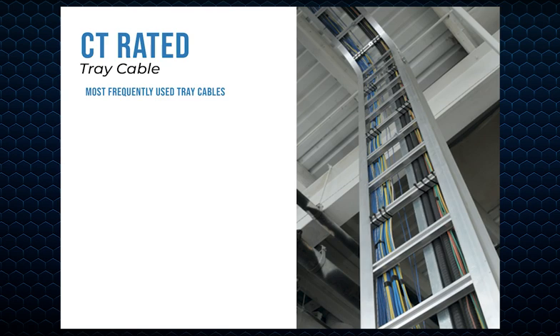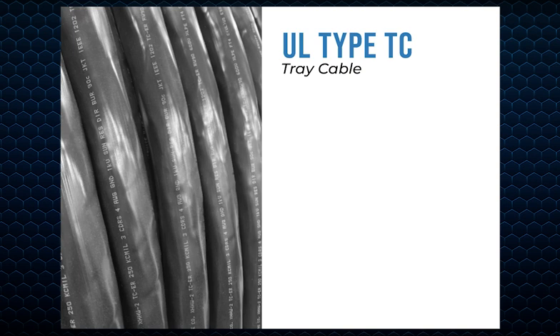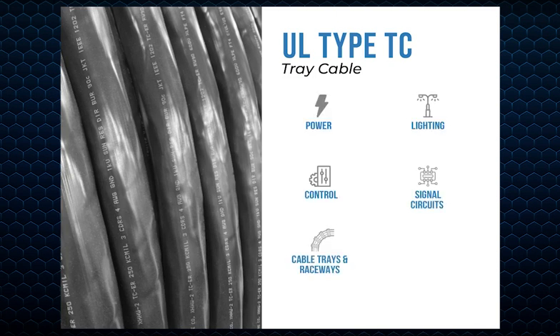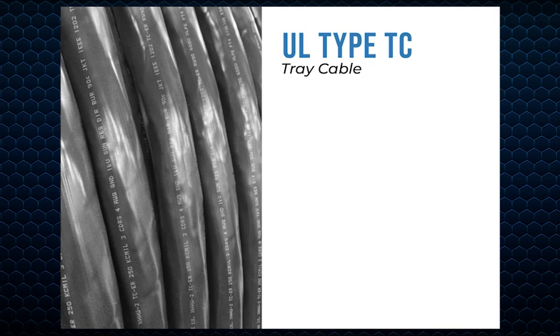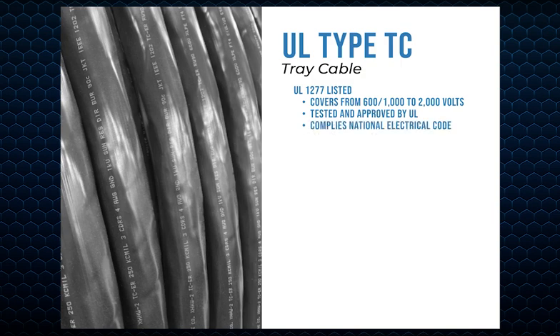The most frequently used tray cables include TC tray cable, PLTC power limited tray cable, and ITC instrumentation tray cable. Article 336 of the National Electric Code identifies where UL Type TC tray cable is permitted. Type TC tray cable can be used for power, lighting, control, and signal circuits in cable trays, raceways, or where supported by messenger wire under certain conditions. Type TC power and control tray cable should be UL 1277 listed, which covers designs from 600 volt/1000 volt to 2000 volts. Products with this listing have been tested and approved by the Underwriters Laboratory, the UL, to comply with the requirements in the National Electric Code.